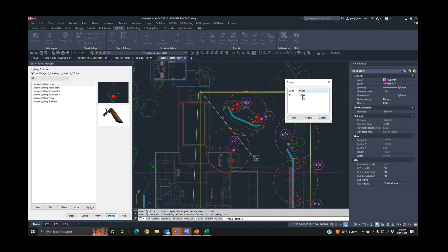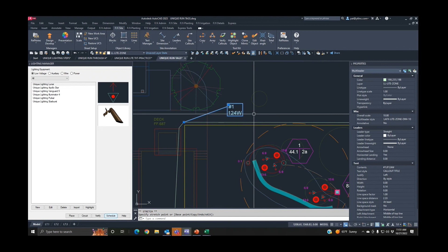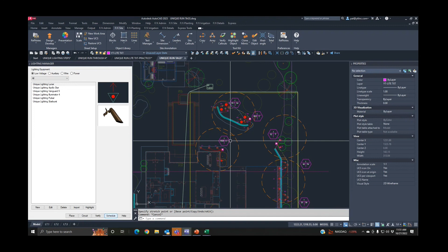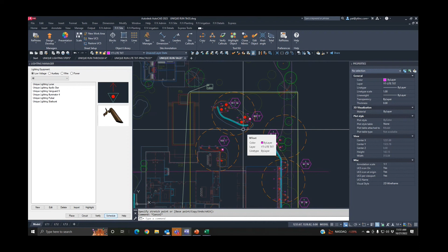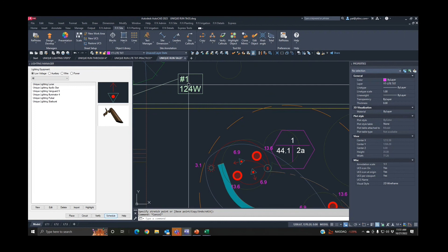We'll say new, and put a fence around all the fixtures we set today. This tells us we have 124 watts total in this area, with this little callout here. So what size transformer do we need to set? The NEC says we can only use 80% of full power on a transformer. The transformers from Unique that we use are 150 watt, 300, and 600. If we look at a 150 watt transformer, 80% of 150 is 120, but we have 124.